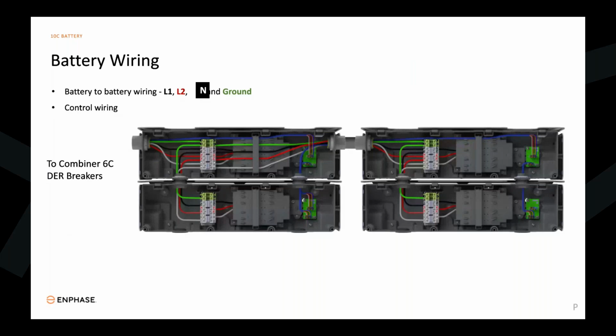When we connect the two batteries together, we use only the wall side to wire those two batteries together. It comes out through the center of that chase into the other battery. Once we get there, we wire it like we did the first one, wiring the wall-side battery of that second unit to its user-side subunit as well. Again we carry over line 1, line 2, neutral and ground into that as well, along with the comms wire, which we'll get into in upcoming slides. But we're not going to go user side to user side when wiring, that's all done through the wall side, through that chase in between. Again, make sure we're always bringing in a line 1, line 2, neutral, and ground from our combiner box. That's a big takeaway: four conductors coming through, using only the wall-side battery units to wire those two batteries together.